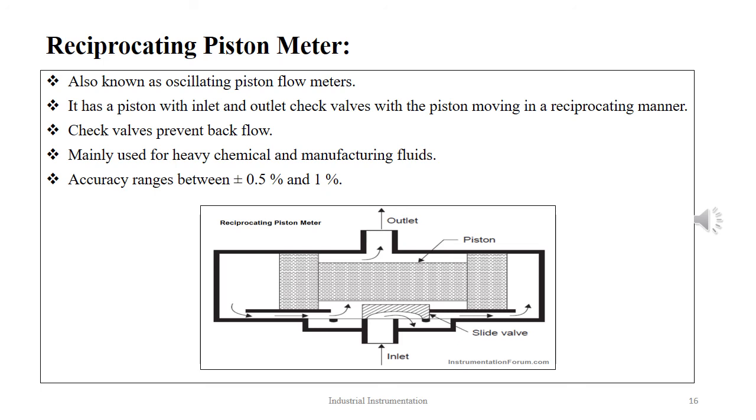As piston retracts from cylinder, fluid is filled in. As piston re-enters, the fluid is forcefully ejected out of the cylinder. It has a very high temperature sustenance capability of 540 degrees Celsius and can handle 100,000 PSIG pressure. These are mainly used for heavy chemicals and manufacturing fluids. They offer accuracy of the range of ±0.5 to 1%.